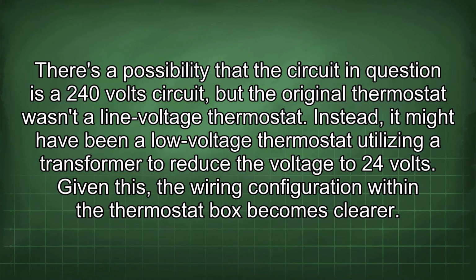There is a possibility that the circuit in question is a 240-volt circuit, but the original thermostat wasn't a line voltage thermostat. Instead, it might have been a low-voltage thermostat utilizing a transformer to reduce the voltage to 24 volts. Given this, the wiring configuration within the thermostat box becomes clearer.